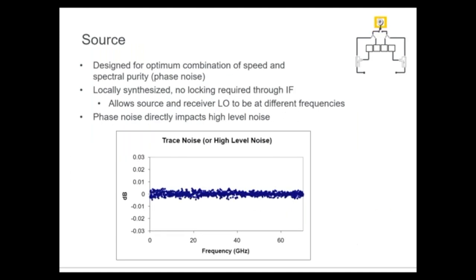The source is also very important because it determines high-level noise, which is related directly to the phase noise of the source. We want a fairly clean source. A lot of the phase noise gets canceled when doing ratio measurements, but we need locally synthesized sources — both the source and the LO that drives the receiver for down conversion need to be independently synthesized. Phase noise translating to high-level noise is a key point, especially as you go higher in frequency to millimeter waves.